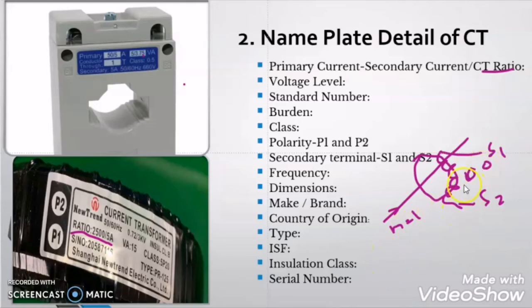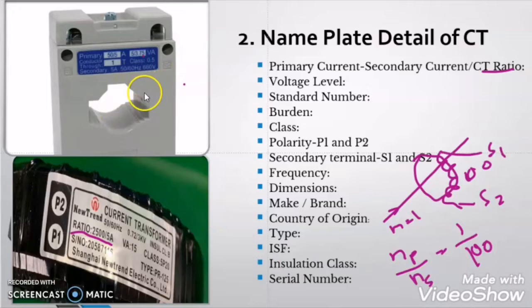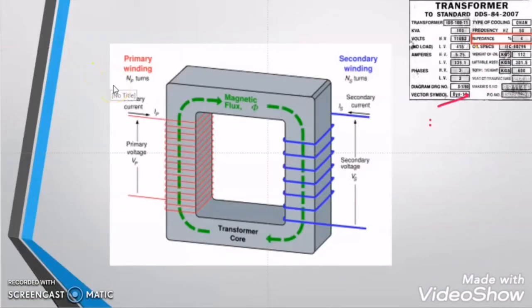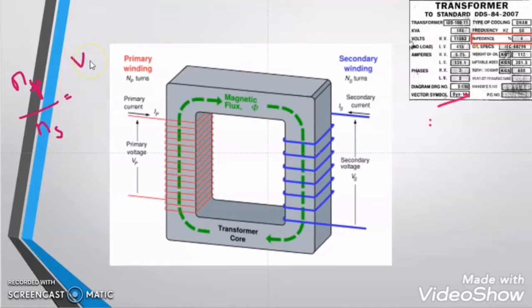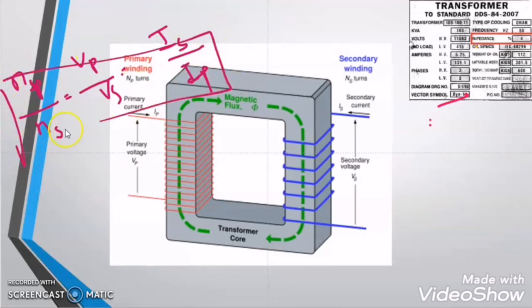So what is the ratio of turns in primary winding and secondary winding? That is primary winding turns divided by secondary winding turns, equal to 1 by 100. As I told in my previous video, the current transformer and the power transformer working principle is the same. So what we have learnt from the power transformer is that the ratio of the primary winding turns to secondary winding turns is equal to the voltage in the primary divided by voltage in the secondary, which is equal to the current in the secondary divided by current in the primary.